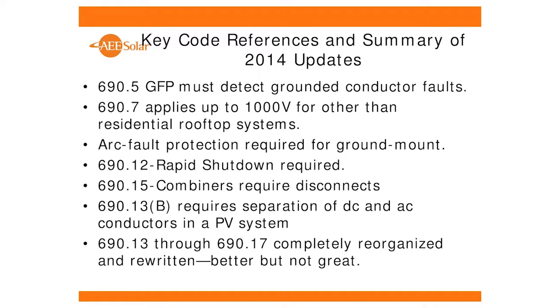Arc fault protection now required in ground mounted systems. That was another big change in 2014 code, not just roof mounted systems. 2017 code does a little more modification on that, but one of the biggest things that was added to the 2014 code was rapid shutdown requirement. That rapid shutdown requirement is fairly short as far as the words, and so there have been, as expected, some enforcement issues with that, but we intentionally tried to keep it short so that we didn't over-specify how to do things, but it does require that conductors leaving a PV array be shut down, and the 2017 code goes quite a bit further than that.